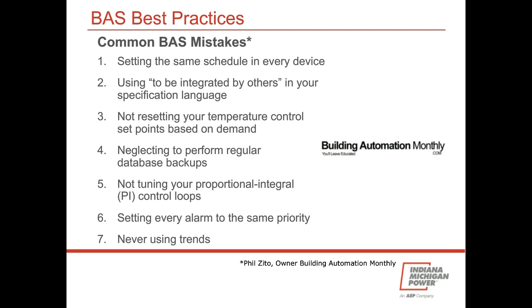Another one - don't set every alarm to the same priority. Not all alarms are equal, as, for instance, you're sitting in front of your user interface and you just got 14 filter alarms, 5 exhaust fan status alarms, 3 zone temperature alarms, and 1 chiller down alarm. Of course, by this point the chiller down alarm is on the next page of the alarm screen, and as they say, out of sight, out of mind. So you really have to prioritize what's really important, super important, and what's less important - keep the most important things right in front of you.